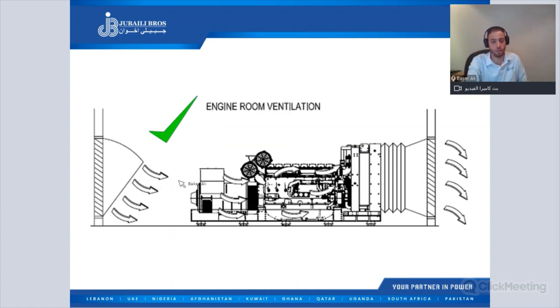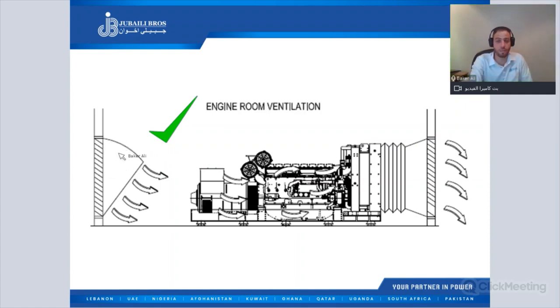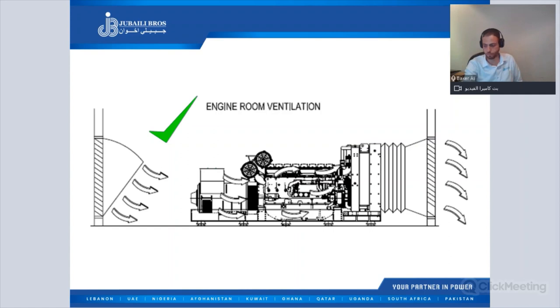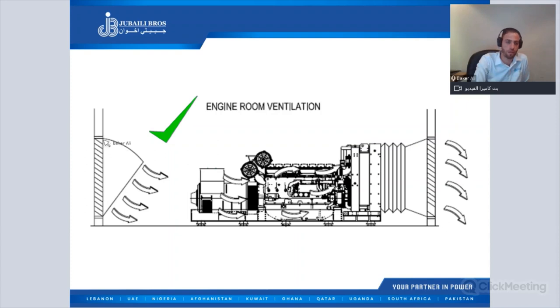The third system, which is also acceptable, has the air inlet position at the high wall. This system is acceptable if we fix a duct here to direct the airflow to the alternator and air filters. If we have the opening at a high level on the wall, we must fix a duct to direct the air to the alternator and air filters, and then the air will pass to the engine and out — so this system is also acceptable.